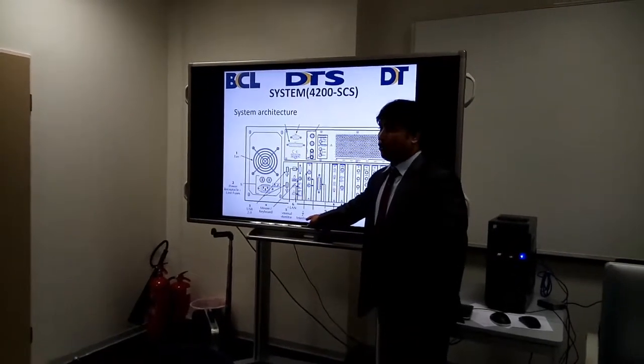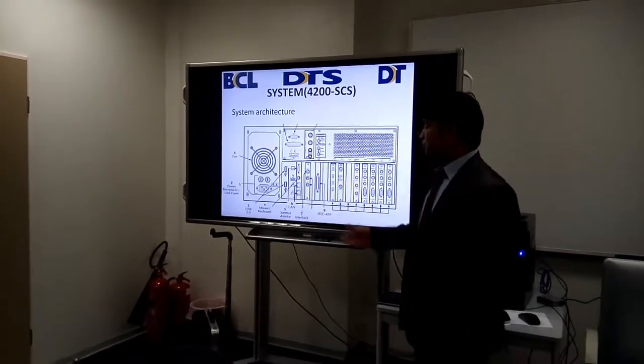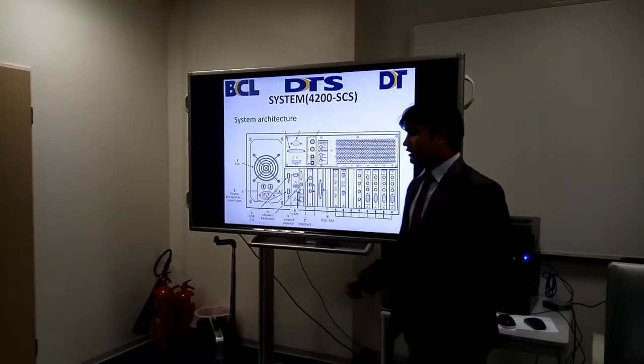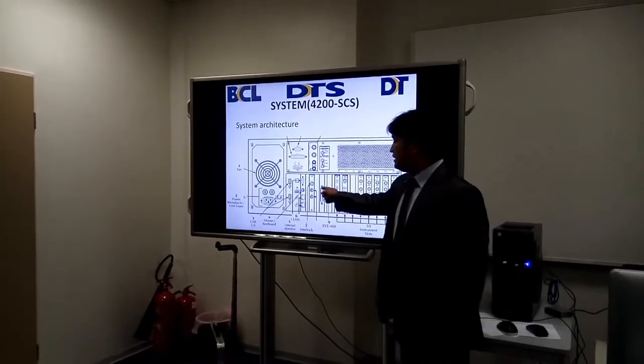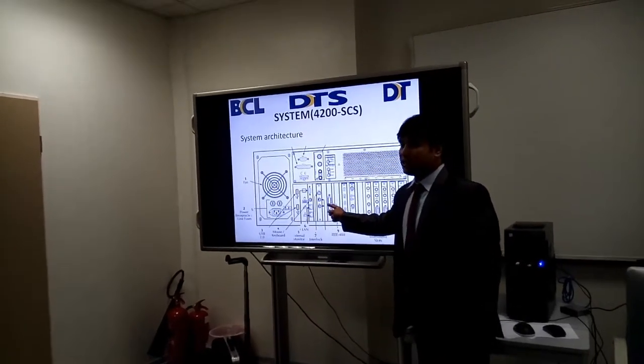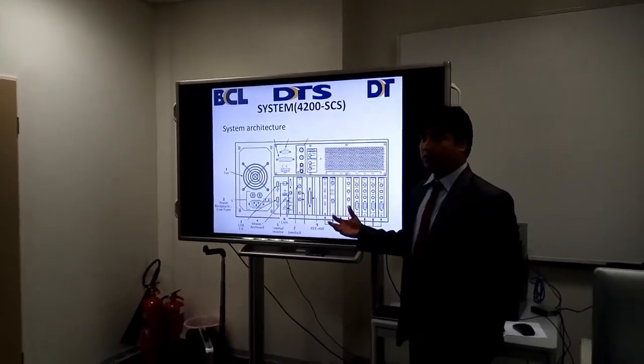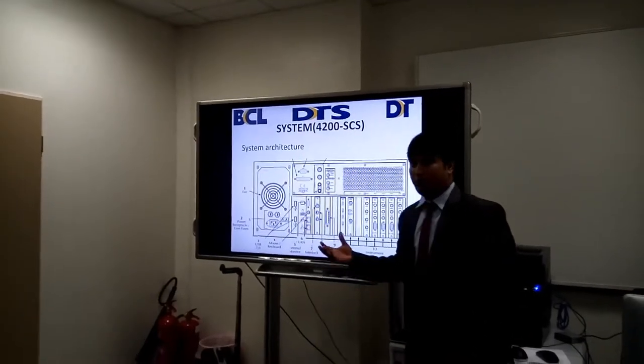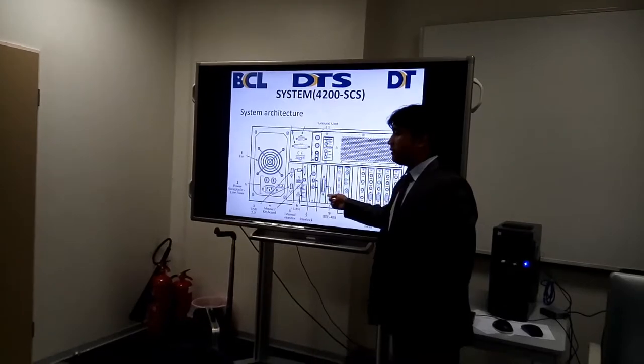There is one option for the interlock. If you want to work beyond 20 volts, there is one standard circuit to activate your high voltage application. We have to make the interlock circuit so that it can go beyond 20 volts. This is called the GPIB connection. GPIB connection is responsible if you want to communicate with this system using LabVIEW. Some people are very expert in LabVIEW and make programs, but it is complex to write advanced programs to use the system this way. If you are very good at programming, then you may connect and go for the programming.